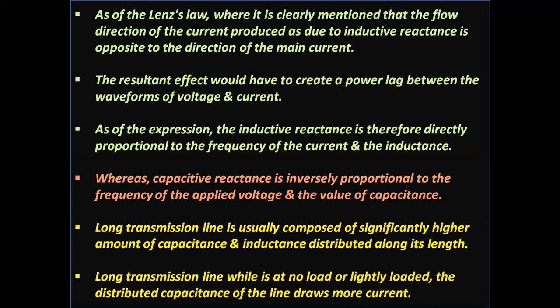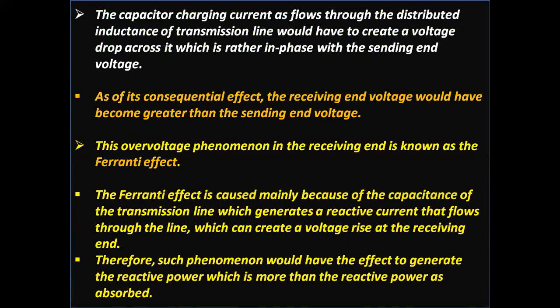A long transmission line is usually composed of a significantly higher amount of capacitance and inductance distributed along its length. When a long transmission line is at no load or lightly loaded, the distributed capacitance of the line draws more current. The capacitor charging current, as it flows through the distributed inductance of the transmission line, creates a voltage drop across it which is in phase with the sending end voltage.